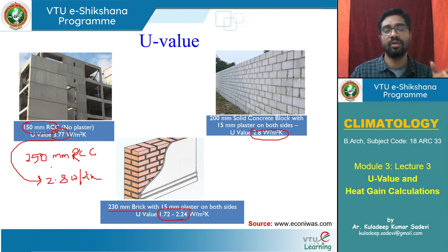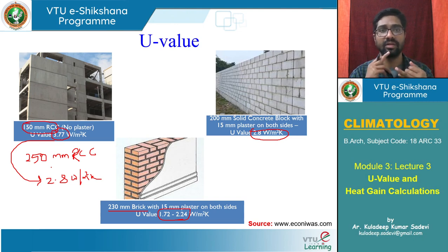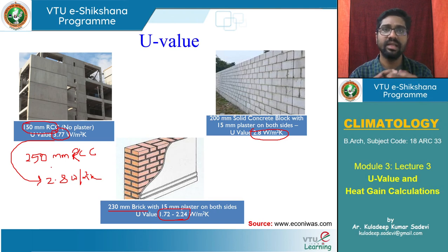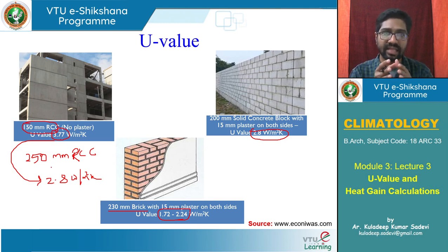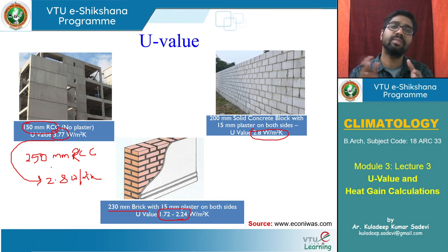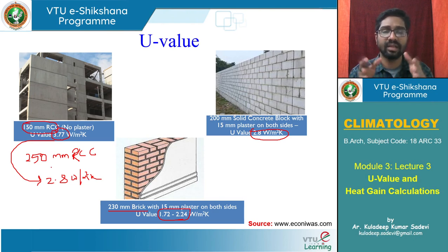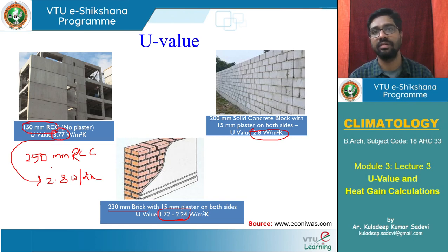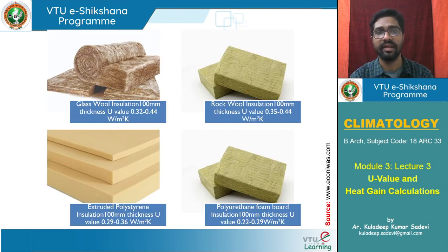Instead of increasing the thickness of the same material, we can add another material as an extra layer that offers better resistance. These two or more materials acting together as one material offer better resistance to heat flow. These are insulating materials. There are four different insulating materials generally available: glass wool, rock wool, polyurethane foam board, and expanded/extruded polystyrene.